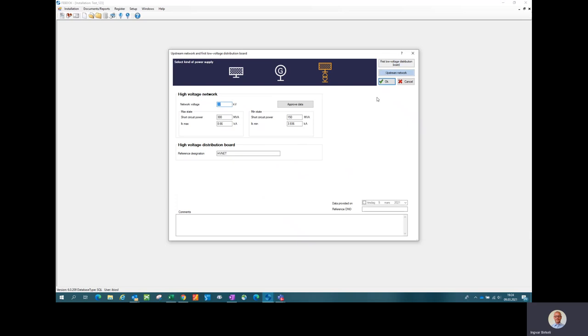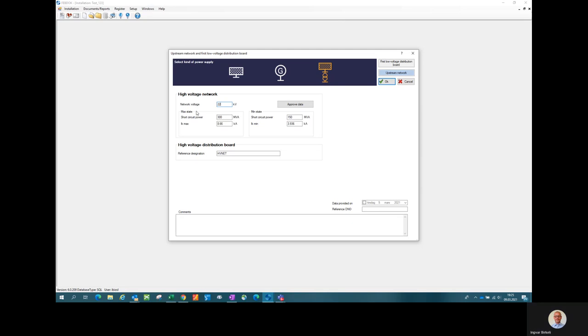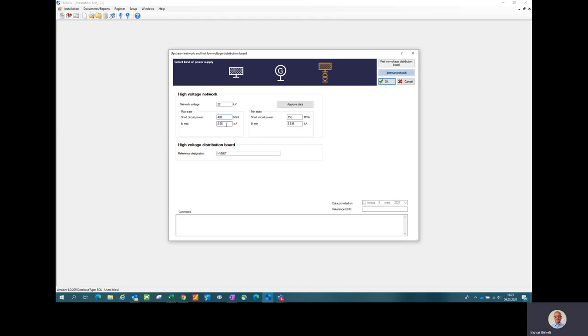Now this is done. I have to take care of the upstream network, the medium voltage supply. I have to select voltage level, 22 kilovolts or 11 kilovolts is mainly used. And here we have to choose or define the short circuit power that the grid can supply. Max state, Fabdoc suggests 300 MVA. In many cases that's okay. If you don't know, I usually choose this to 400.